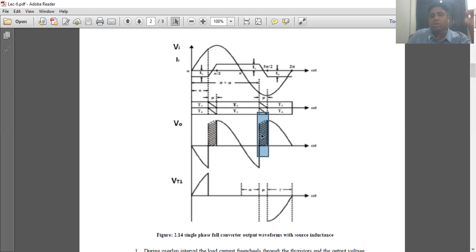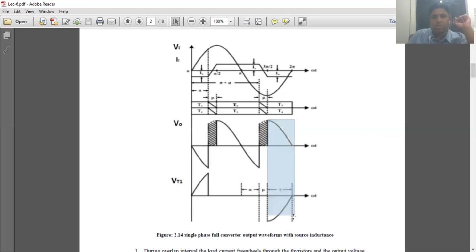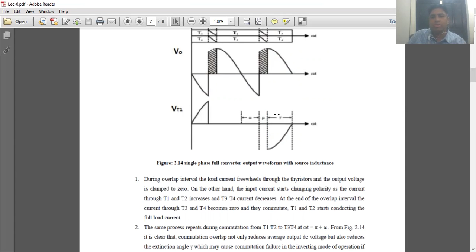Okay, it is clear that commutation overlap not only reduces the average output DC voltage, but also reduces the extinction angle gamma, which may cause failure in the inverting mode of operation if alpha is very close to 180. So due to overlap, first, during this shaded portion you have zero output voltage, so the output DC voltage is reduced. The second effect is that gamma, the extinction angle, will also reduce. The more the overlap, the less the extinction angle, and this problem becomes serious if alpha is equal to 180 in inversion mode, where gamma will basically go to zero.